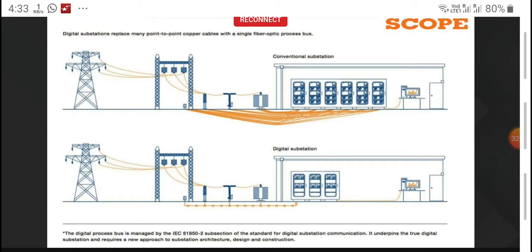But when it comes to digital substation, most of the auxiliary relays are being eliminated. If it is a tripping in a conventional or SAS-based system, you still use the master trip relay to trip the breaker. But in the digital substation, when a fault happens, the relay detects it and gives the trip command through the GOOSE message to the breaker. The GOOSE message will flow from the relay to the breaker in digital format, and from the breaker end it will recognize it as a trip command and trip. So you don't require a master trip relay additionally, where your relay itself directly gives the digital signals to control the breaker.